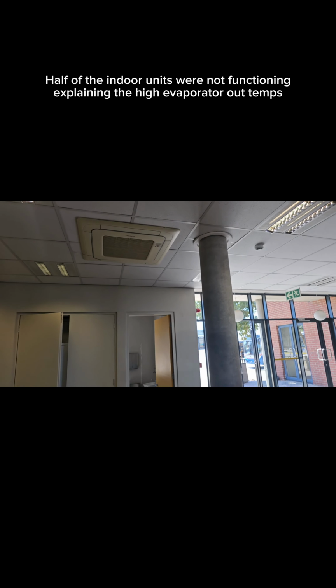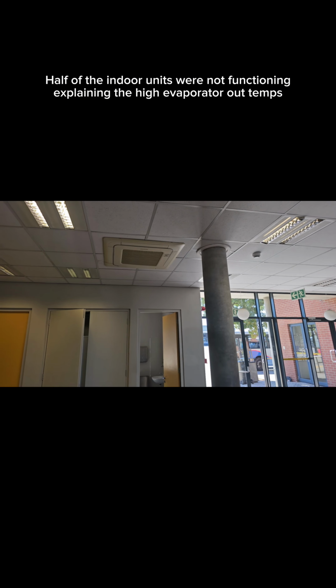So I need to figure out why that is, and that could be the reason why we see the big difference on our evaporator out compared to our suction line temp at the condenser, because our suction line temp at the condenser is 5 degrees, but our units over here, even upstairs, these ones will be a lot lower, but upstairs they are struggling to come below 20 degrees. So what I'll do is I'll do a unit count, change the settings on the condenser, and see if we are able to get these systems to operate.